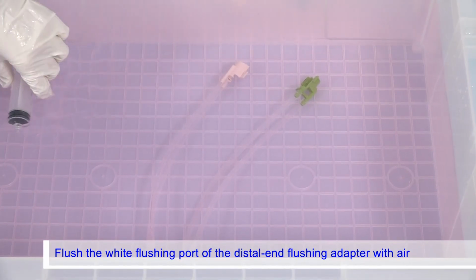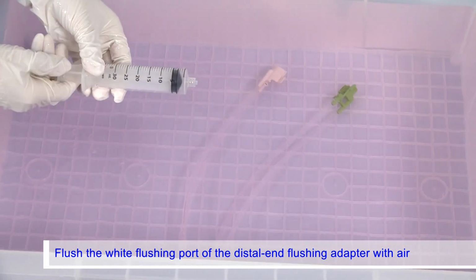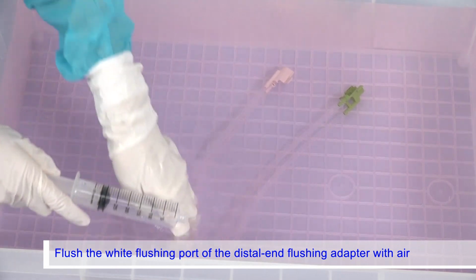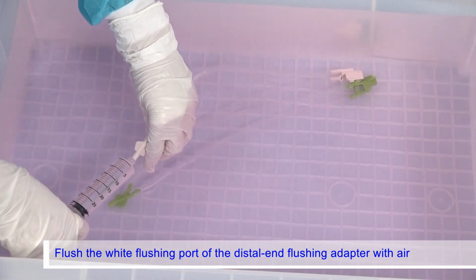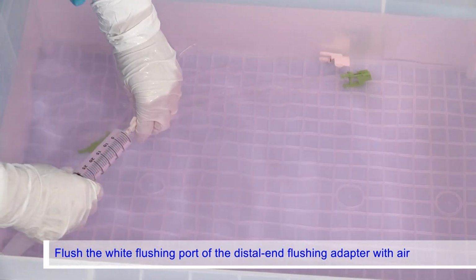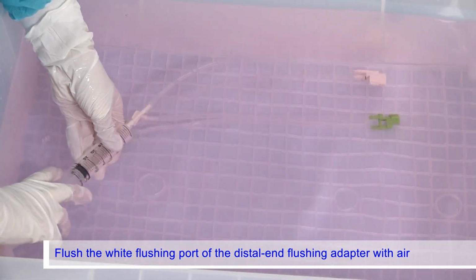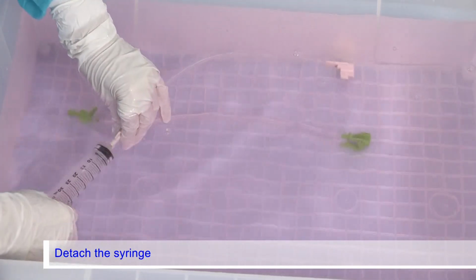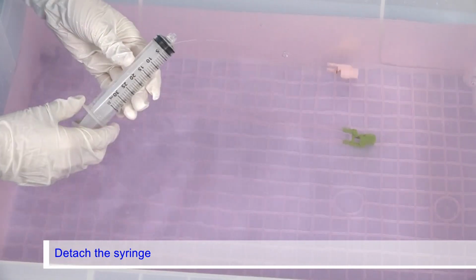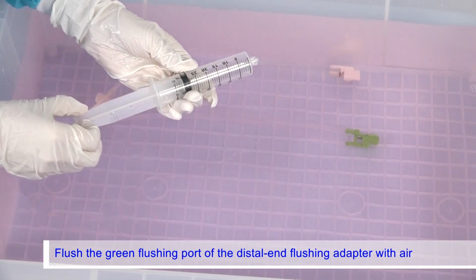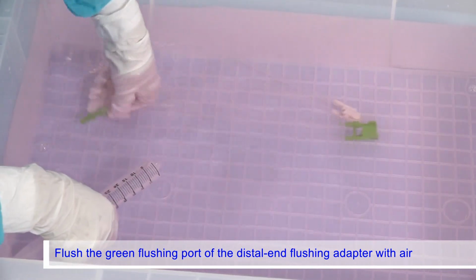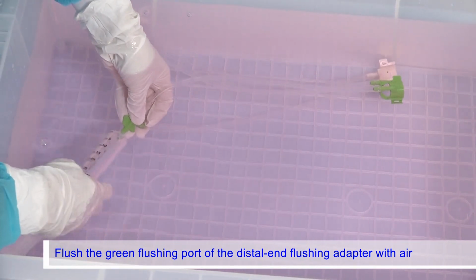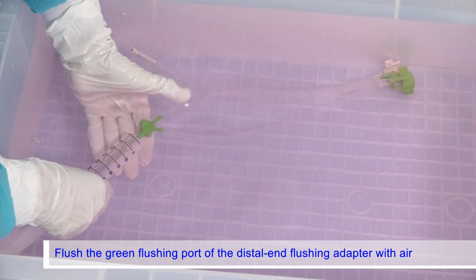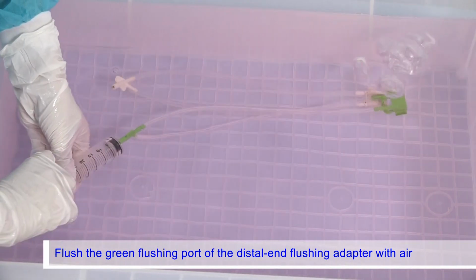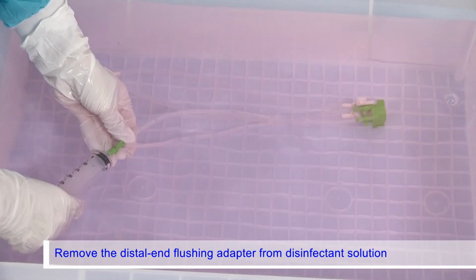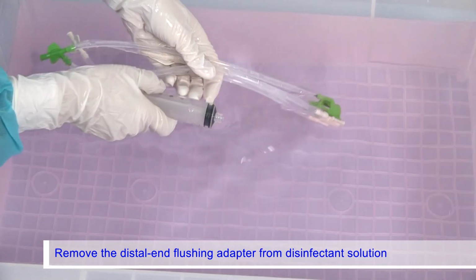Fill the syringe with air, attach it to the white flushing port of the distal end flushing adapter, and flush the adapter with 30 milliliters of air. Detach the syringe from the flushing port of the distal end flushing adapter. Fill the syringe with air, attach it to the green flushing port of the distal end flushing adapter, and flush the adapter with 30 milliliters of air. Remove the distal end flushing adapter from the disinfectant solution.